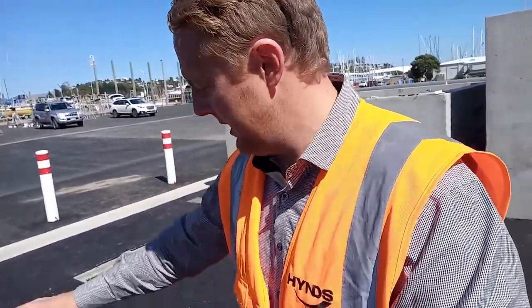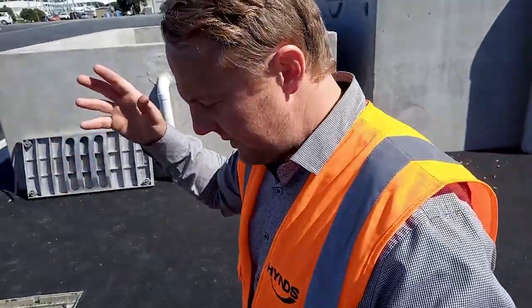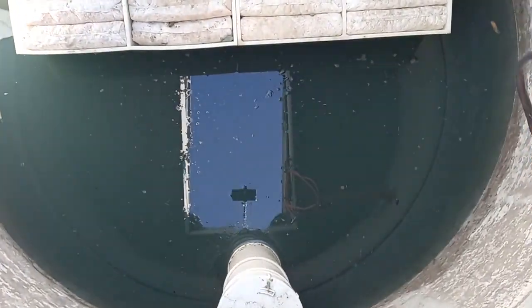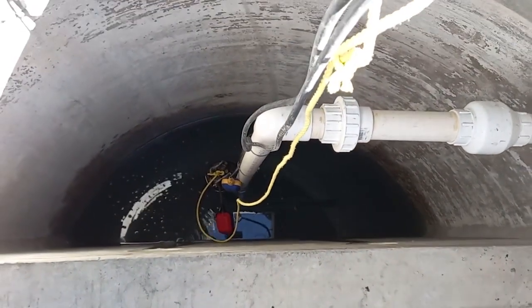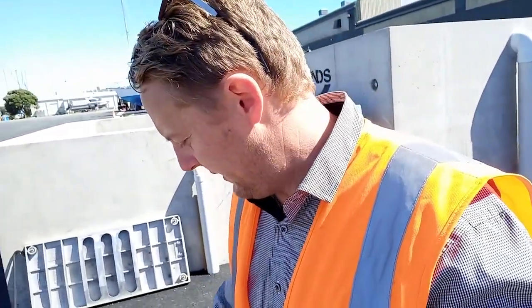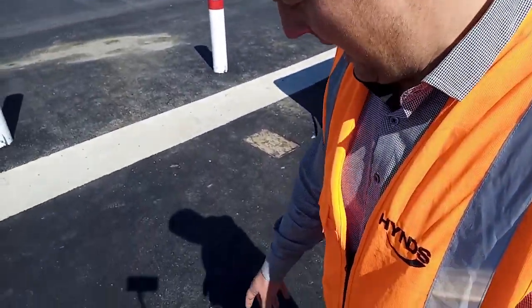So from the Enviro valve, it goes to both the pump stations. These are two 1800 diameter manholes which we supplied, designed. This one's the stormwater. So inside there's essentially a 4-bay, which is going to provide a high degree of settlement. There's a wet sump there, and all the stormwater, as with the trade waste, is going to pass through the smart sponge filter packs. Those are going to absorb the hydrocarbons. We really want to prevent any hydrocarbons from contaminating the sand and peat media, so it's best to keep them separate. That's also going to remove a lot of the finer silt, down to the 20 micron range.